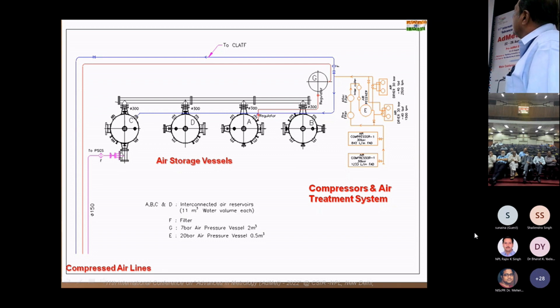From there, it passes through two dryers connected in parallel, which maintain the dew point temperature. From there, it stores the air in these four vessels. All the vessels are connected to the manifold with valves, and this air we take to the gravimetric system. We can also take this air to the closed loop system. Here we have a small 2 meter cube vessel, at 7 bar, which is used for actuation purposes and for instrument air. So these are the air storage vessels and compressor systems.